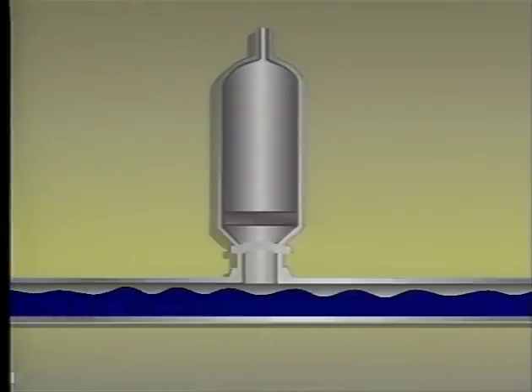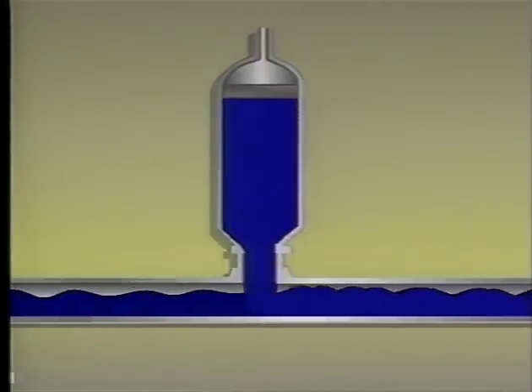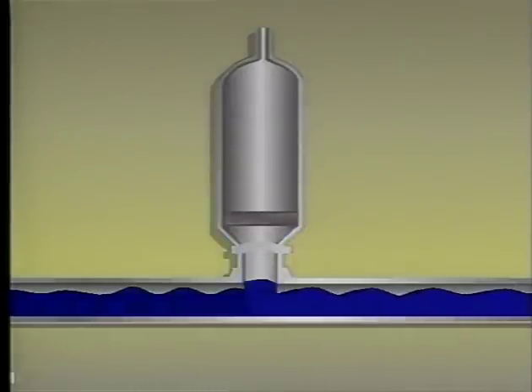When the forward motion of the water column is stopped by the valve, part of the reversing column is forced into the water hammer arrestor. The water chamber of the arrestor expands at a rate controlled by the pressure chamber, gradually slowing the column and preventing hydraulic shock.